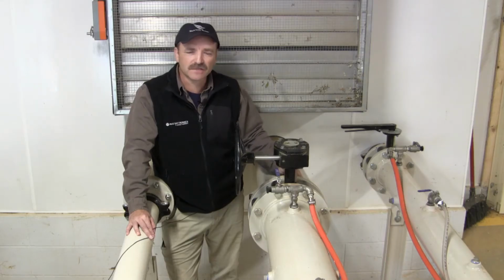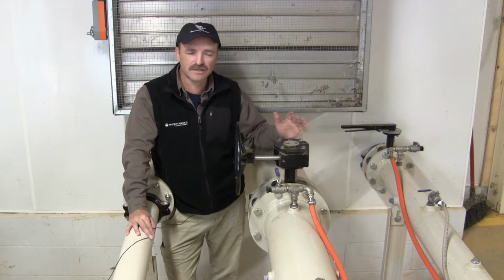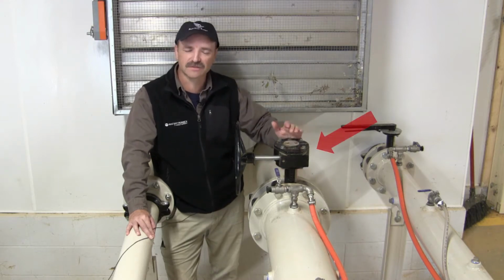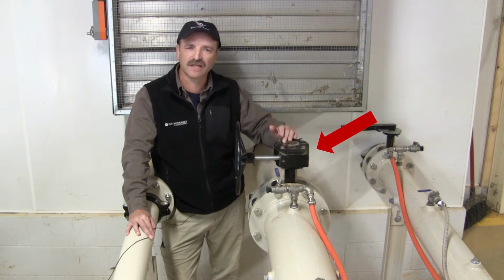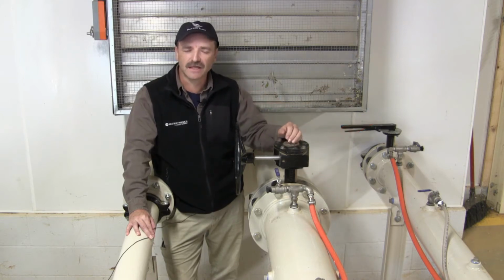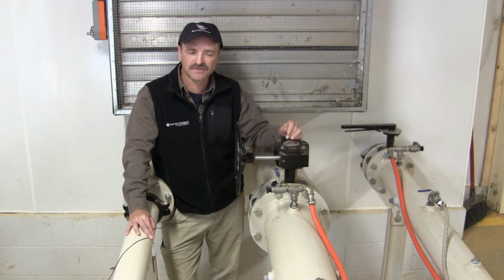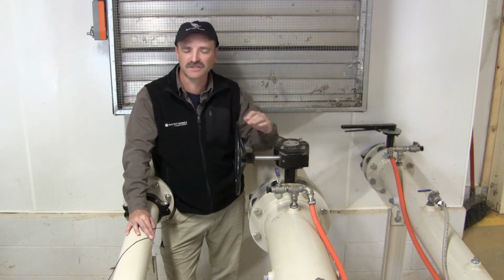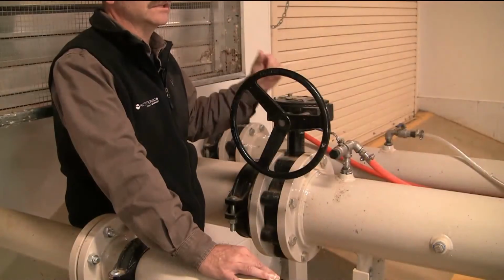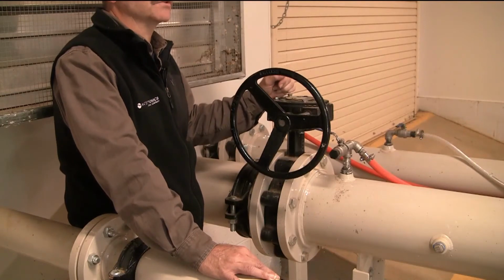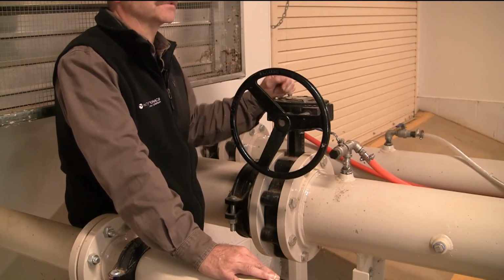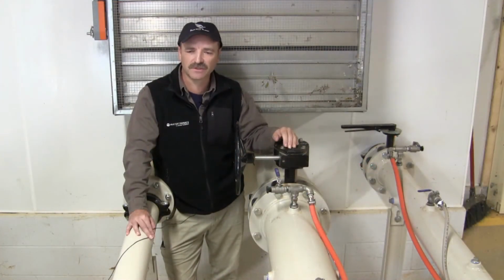So we'd like to talk to you a little bit about the terminology that goes with a pump station, and we're going to start here on the way out of the pump station. This is the main discharge valve that heads out to the field, and if you've got an issue on the pump station, the first thing you want to do is come and close this, which is going to keep that pressure in your system and also keep the water from dumping all over the floor of your pump station. So remember, if you got a problem, you come in the building, shut your pumps off, and then come over and shut your main discharge valve.